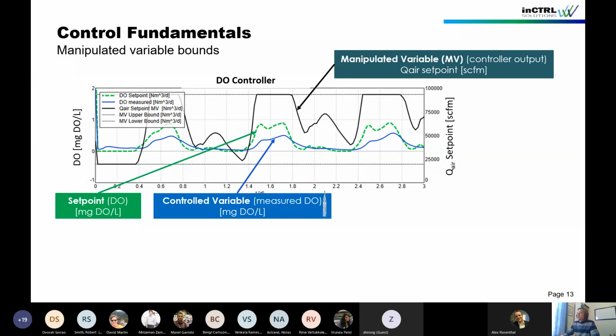So this is basically protecting your equipment or your process. And this is very, very important to understand because this is one of the main limitations you have in practice. If you are hitting one of these bounds, you cannot further maintain the set point. You can nicely see that here. This is, in this case, the airflow set point. So it goes up, hits the upper bound, and you see that suddenly there's a difference between set point and controlled variable. And that is, of course, because the controller wants more air, but reaches a maximum. So there's not enough air going into that tank.